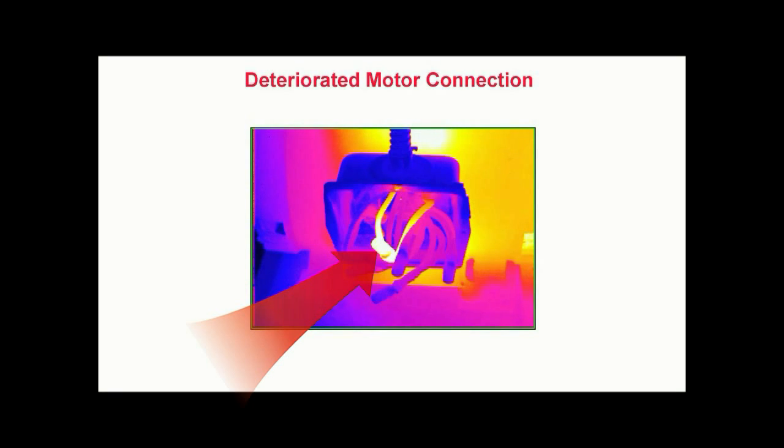In this image, we see localized heating, shown in white, at one of the splices, which typifies a loose connection.